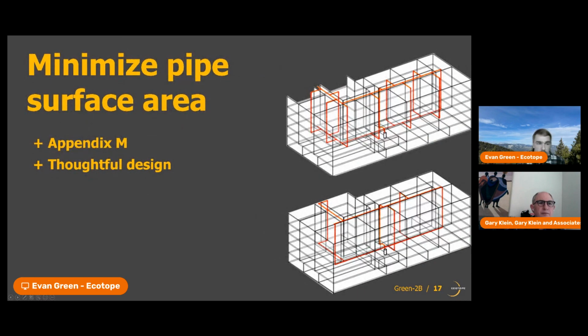The first way we're going to minimize these heat losses is to minimize the surface area of the pipe. The surface area is accounted for in two ways: the diameter of the pipe, which drives the circumference, as well as the length of the pipe. In order to decrease the diameter, we're going to need to size these pipes properly for the peak flow that they will see throughout the life of the building. Currently, most jurisdictions will refer to the Hunter's curve, which was created back in about 1940, which is a really long time ago when fixtures were a lot different.